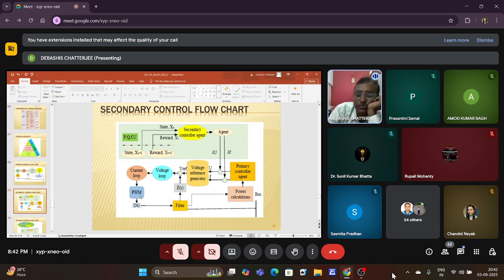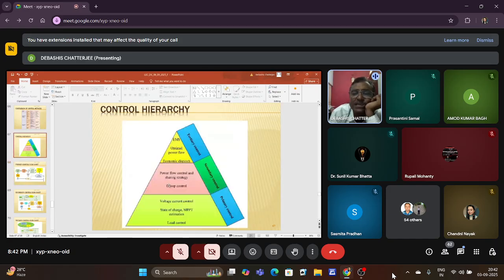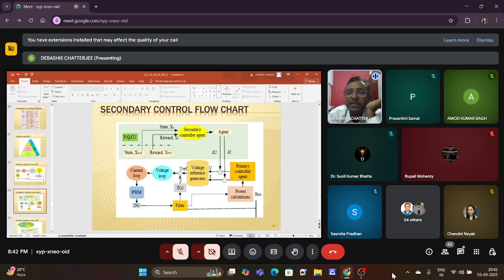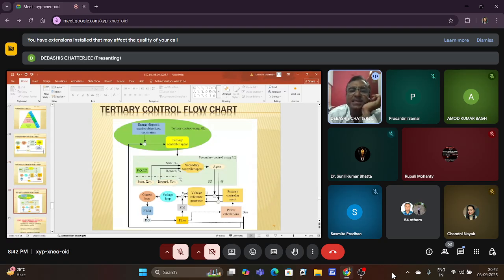Taking into account things like droop, sharing strategy, or power control as required, the tertiary control gives economic dispatch, energy dispatch, and uses machine learning algorithms, producing a tertiary control agent output that feeds the secondary controller, which again uses it to refine its delta U and delta F.